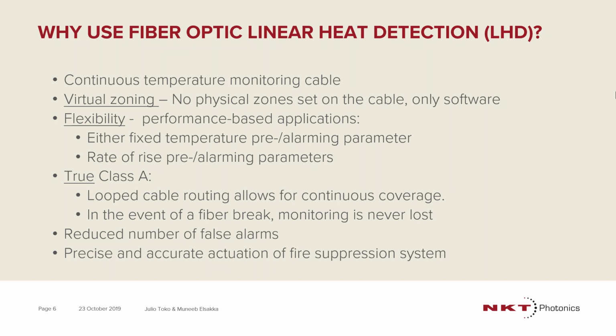You have flexibility of using either fixed temperature or rate of rise, pre-alarm and alarming parameters. You can do a true Class A looped cable routing to ensure maximum coverage. So in the event of a fiber break, you do not have any coverage lost. Reduced number of false alarms, and you have precise and accurate actuation of a fire suppression system. This allows you to set up zones and actuate fire suppression systems only in the hazard of interest.